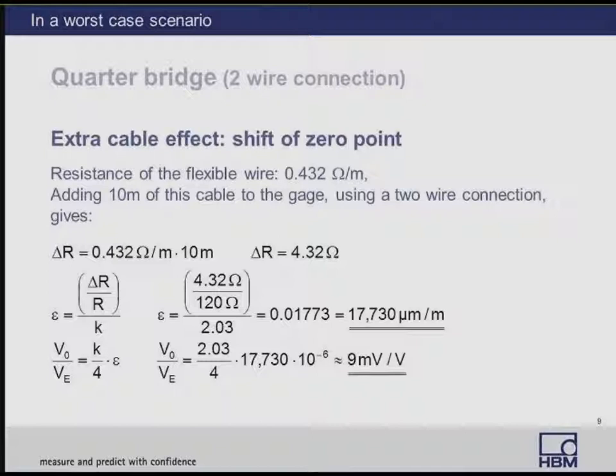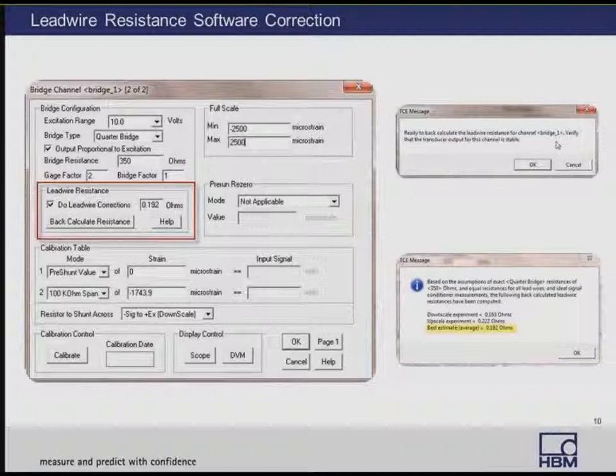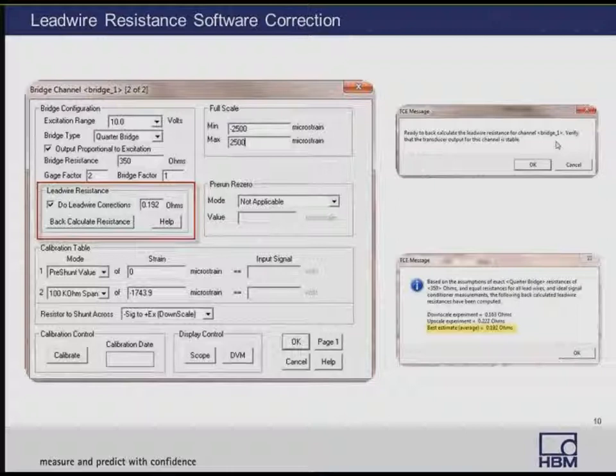HBM products have different ways of handling these issues. For the EDAC control package, we can use the lead wire resistance panel to have the software calculate the amount of lead resistance and perform a correction. This can be manually calculated based on wire gauge and wire length. Using the back-calculate resistance button, we apply excitation to the bridge and make measurements after applying shunt resistors to various arms of the bridge to determine what the lead wire resistance actually is, which can then be manually entered into the lead wire corrections field.